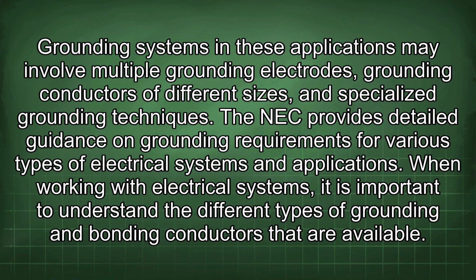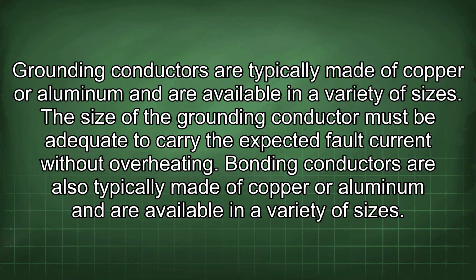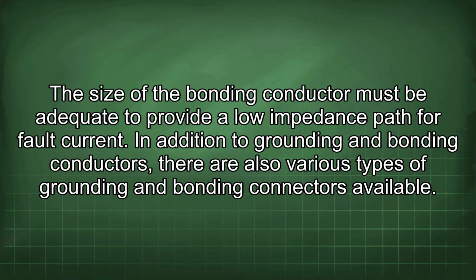When working with electrical systems, it is important to understand the different types of grounding and bonding conductors that are available. Grounding conductors are typically made of copper or aluminum and are available in a variety of sizes. The size of the grounding conductor must be adequate to carry the expected fault current without overheating. Bonding conductors are also typically made of copper or aluminum and are available in a variety of sizes. The size of the bonding conductor must be adequate to provide a low impedance path for fault current.